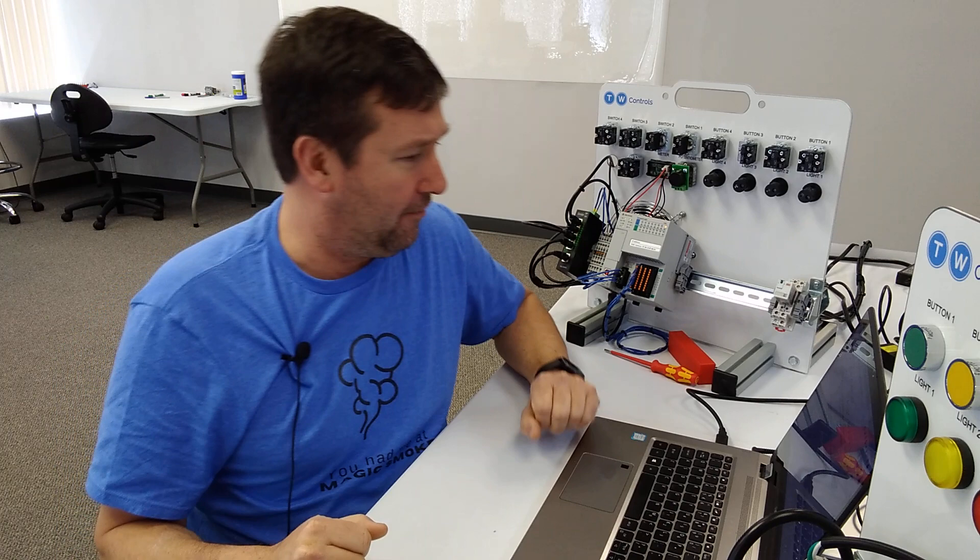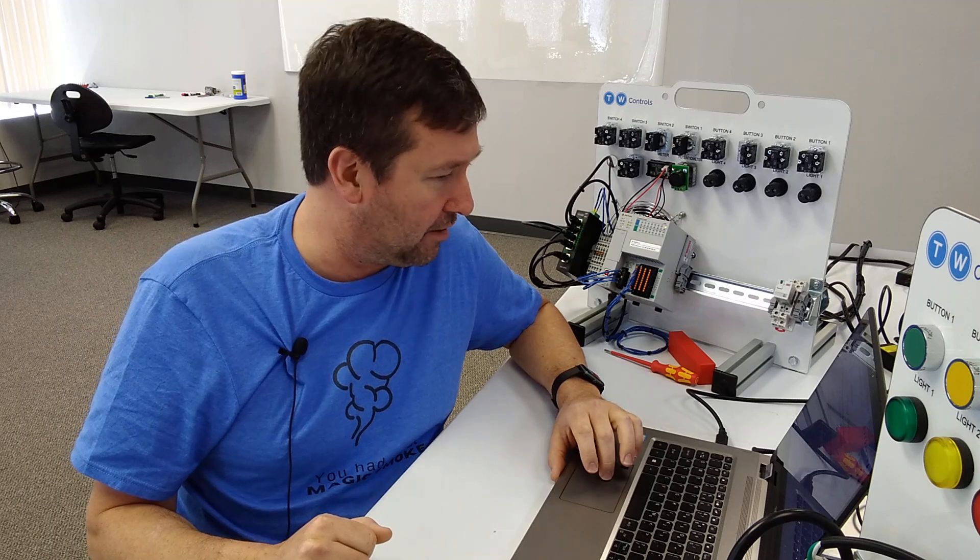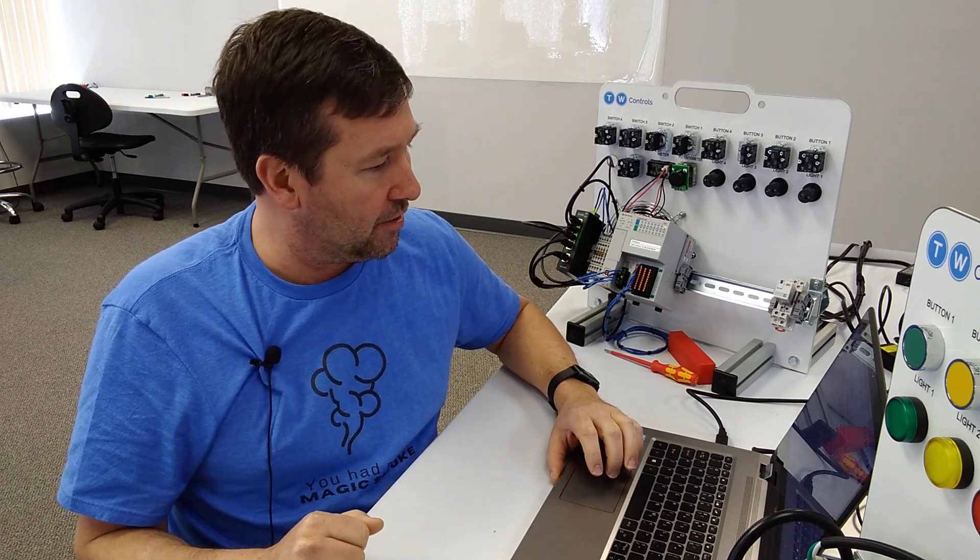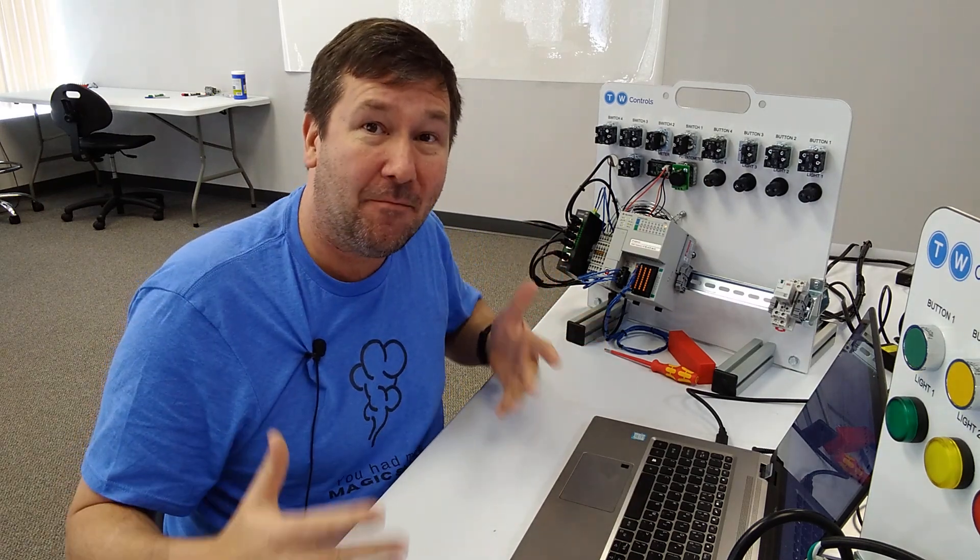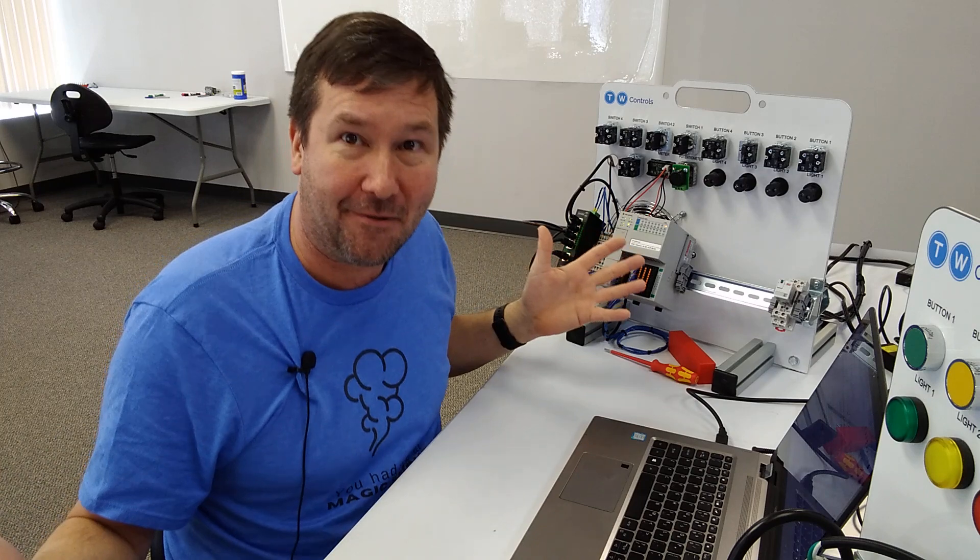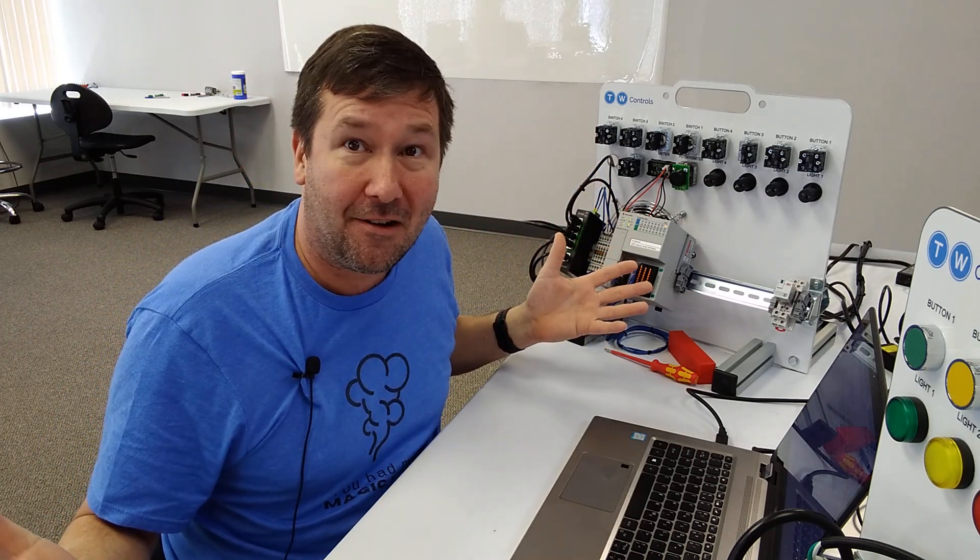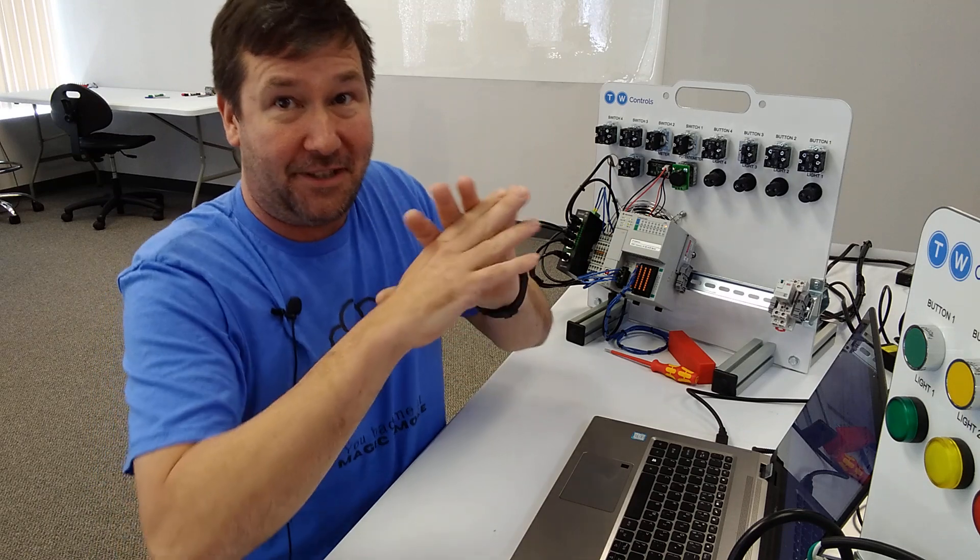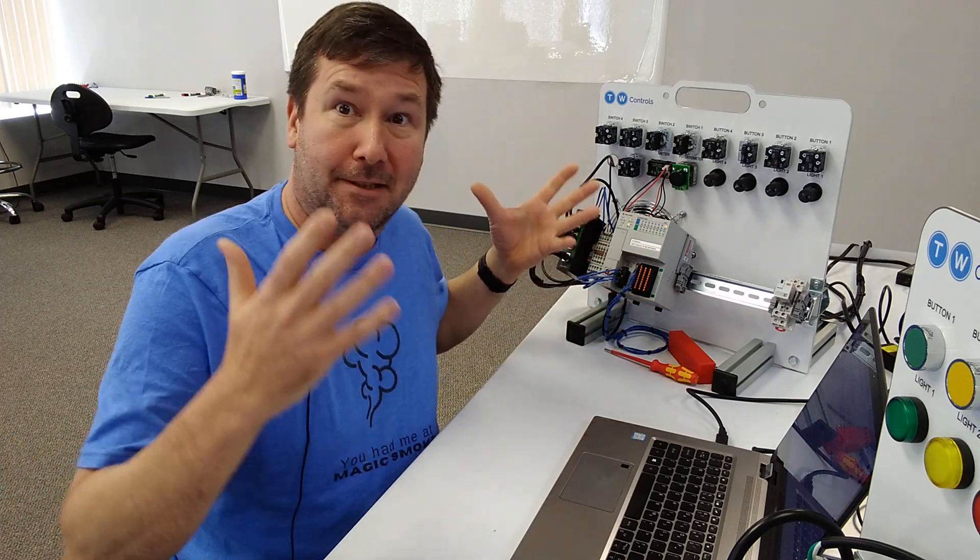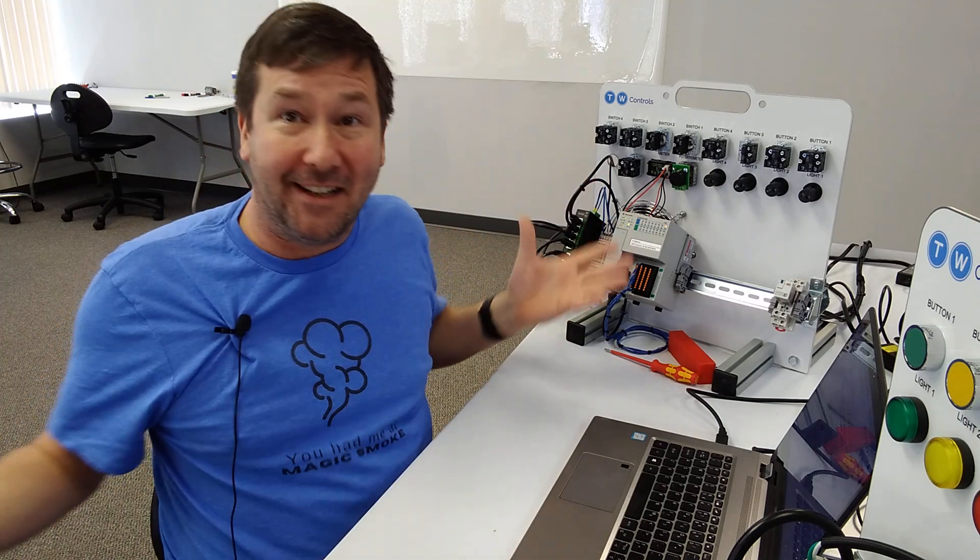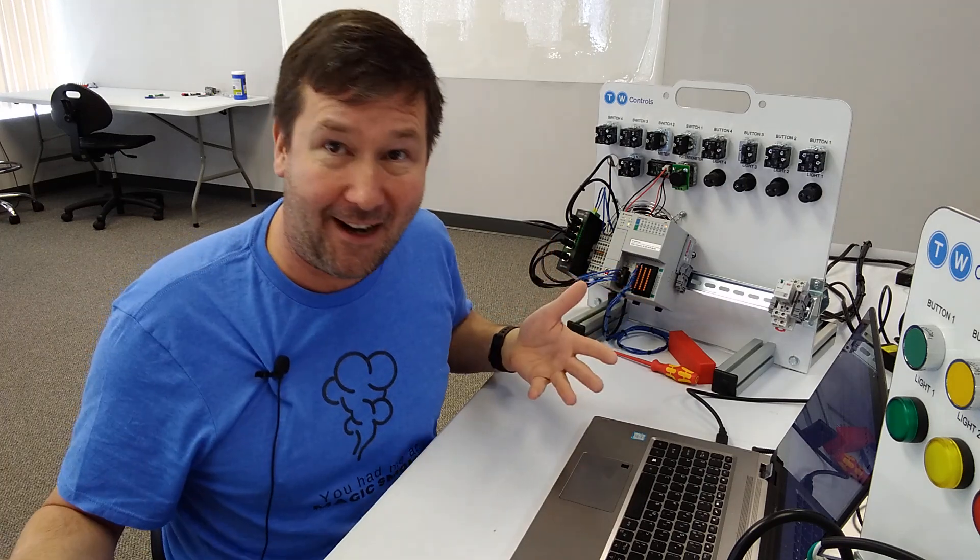Next, we have awesome video. Set the part where you're prodding around in a panel without electrical safety precautions. And there's 480 supply to the transformer. Pretty sure that violates OSHA 1910-137. Well, no, it's not. 1910-137 is specifications about PPE. It has nothing to do with when or where you're going to wear it. So if you're going to call me out in a video about doing something wrong, at least cite the right code for everybody. Also, make sure that you're calling out the right thing, because no, there wasn't a 480 supply going to that panel. It was a 120 supply going to that panel. We're backfeeding a transformer. Now, in the end, that's just as dangerous. But gosh, if you're going to get technical with all this code citing, get it right.